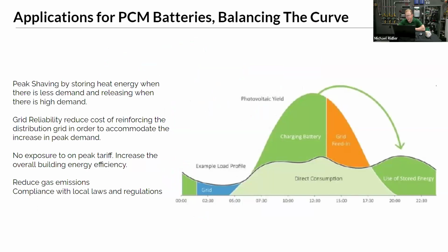One of the things I find really exciting about PCM batteries, especially as we start to adopt air-to-water heat pumps, is the ability to balance the curve, not just store BTUs. In Quebec, there are incentives for thermal storage, so people will start putting in thermal batteries, storing energy electrically to heat their home or provide domestic hot water, and taking advantage of off-peak rates. Like in Ontario right now, we have that ultra low overnight off-peak rate.